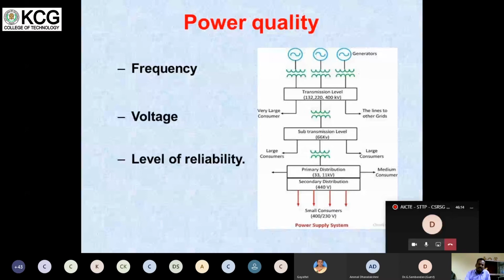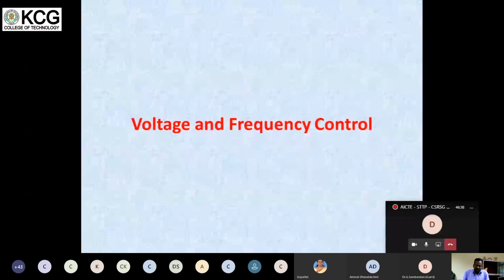Frequency: what is the frequency at the generating station? The same frequency holds up to the consumer end. So whatever frequency at Kanyakumari, we can see the same frequency at Kashmir. But voltage is not like that. Voltage will differ from place to place and depends on the line length and resistance of the line. We say drop in the line. So grid means we have to maintain the voltage and frequency, and voltage and frequency should be controlled. That is the main aim of the grid system.